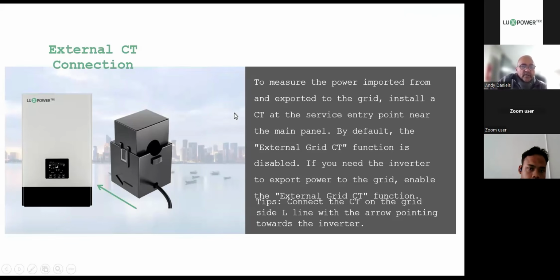All right, so this is what the CT looks like. The ones that we've supplied recently are blue in color, and you can see it's got an arrow on there. See that direction arrow? Your live will go through here, and the arrow will point to the inverter. So it's from grid to the inverter. You see here, the arrow is always pointing in that direction. And if you've got it wrong, you can always go into the settings page and switch the direction of the CT if you've installed it incorrectly, because trust me, sometimes it's a real bother getting into a very dense DB to try and get your fingers in there and turn a CT around.